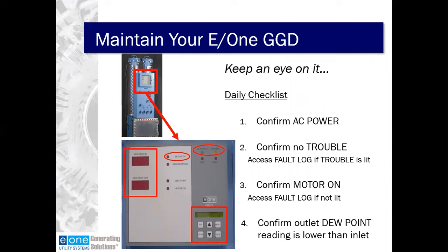The next is to ensure that there is not a trouble alarm, so we want that LED to be not lit. If it is lit, then we've recorded a fault in the fault log. So you would access the fault log to identify what that issue is and then report that to E/One for troubleshooting accordingly. The next LED that's critical for us is that the motor on LED is active. This ensures that the circulating blower is active, circulating the hydrogen through the dryer. If that is not lit, again, there will be a fault in the fault log, and that would be reported back to us for troubleshooting.